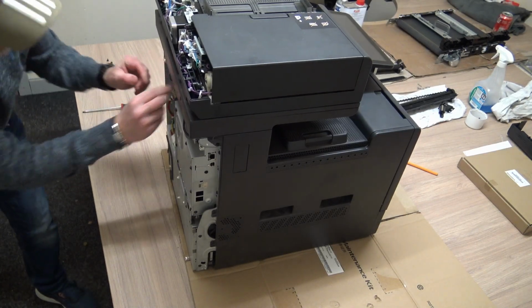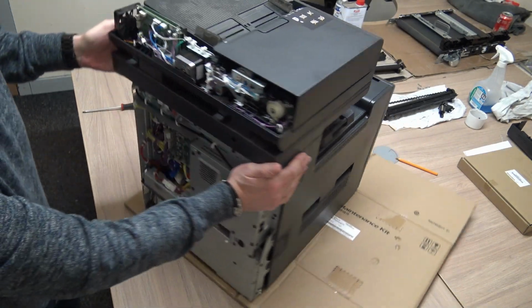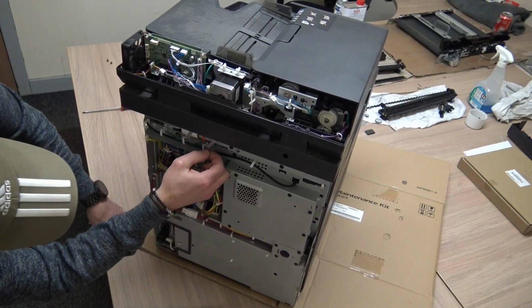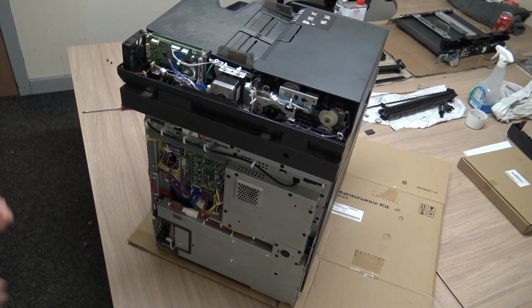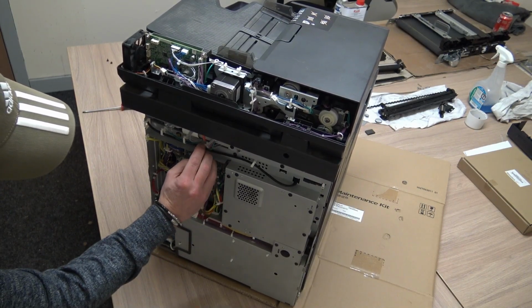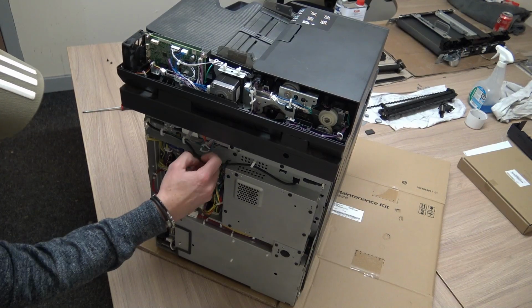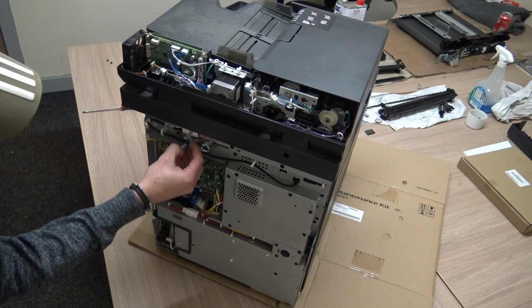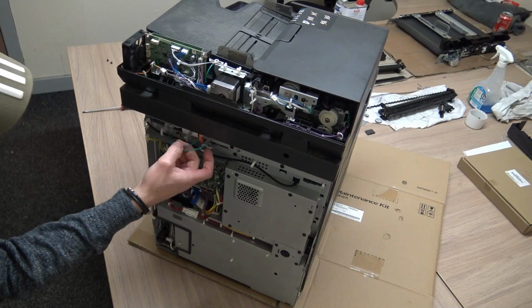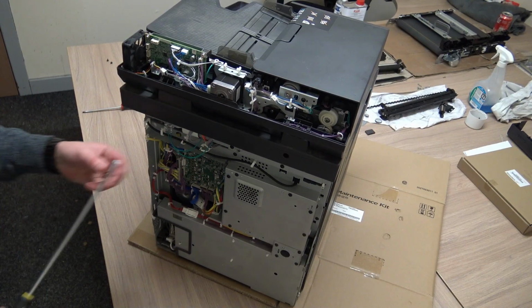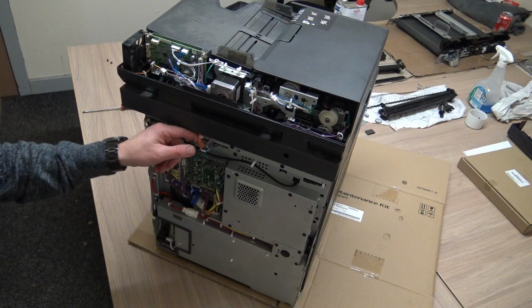Now once that rear cover has been removed, we need to unplug a few connectors, an earthing wire, and a couple of brackets to get access to the cables which are fed through from the actual scanner and document feeder into the back of the machine. So I was just having a quick look around, see how it all comes off.